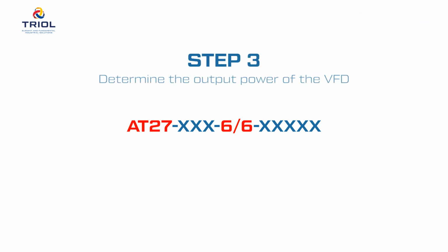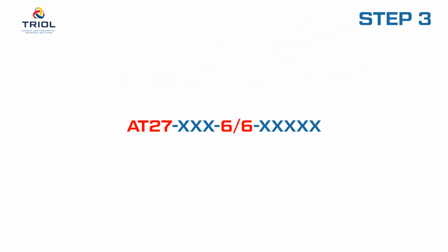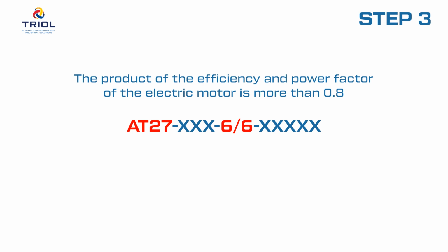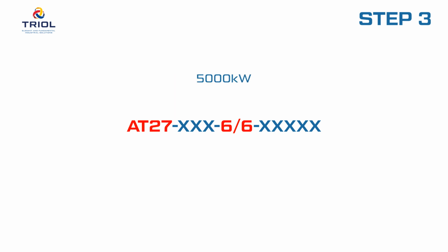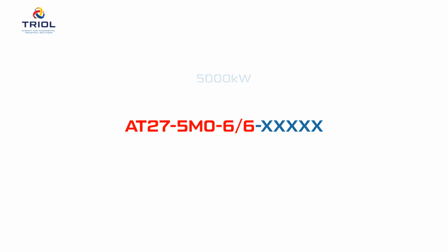Step 3. Determine the output power of the VFD. A sludge aggregate Dresser Rand Datum D16R10B with a 4920 kilowatts electric motor, 6000 volts, 560 amperes. ETA 0.974. Cosine phi equals 0.87. Fan operating characteristic: start up without overload. The product of the efficiency and power factor of the electric motor is more than 0.8. Therefore, the active power of the VFD is equal to the power of the electric motor, rounded up to the catalog higher value of 5000 kilowatts, or in the designation 5M0.